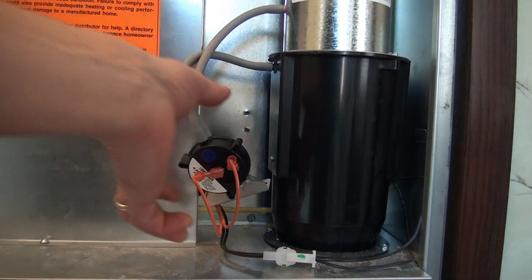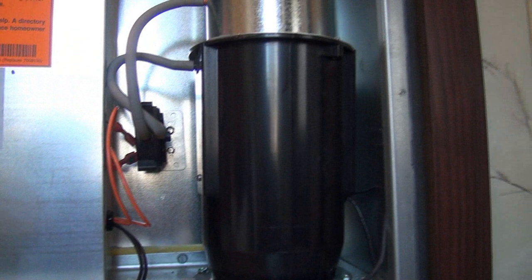Alright, so you can hear that the burner is now going. You can see I've got a solid red and a solid yellow, and of course if you look at your handy chart here, solid red is control okay, and solid yellow is that a flame has been set. So, hoping this video's been helpful.